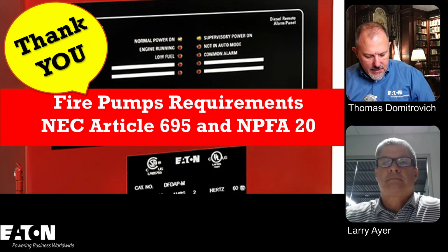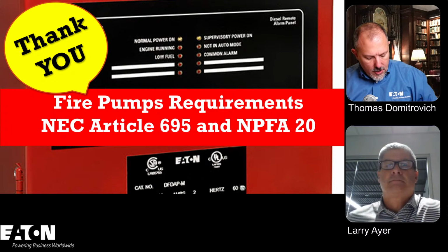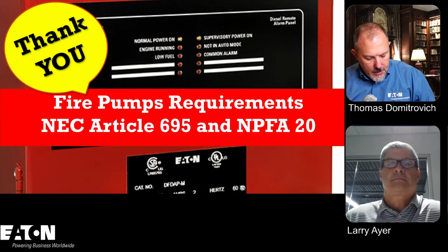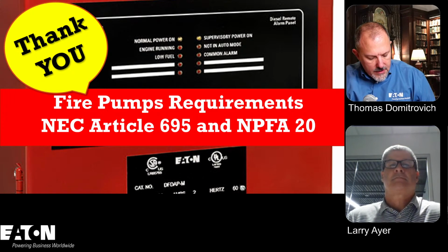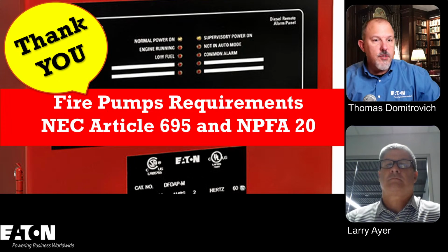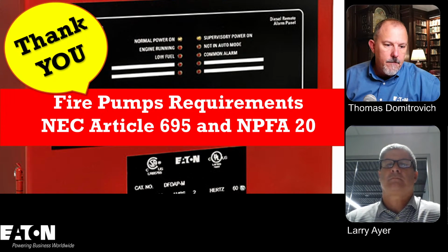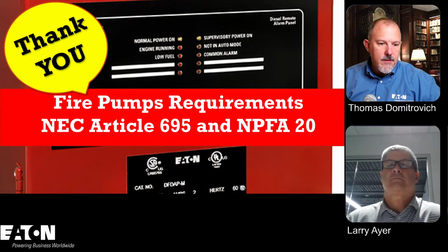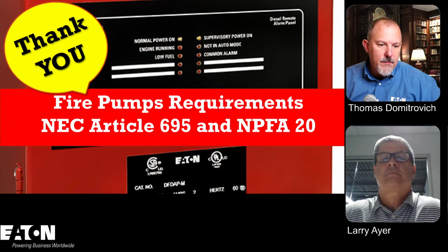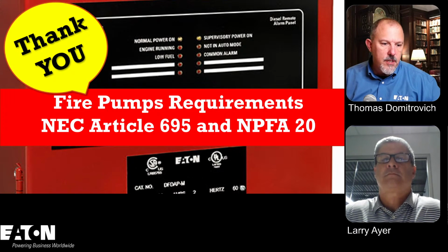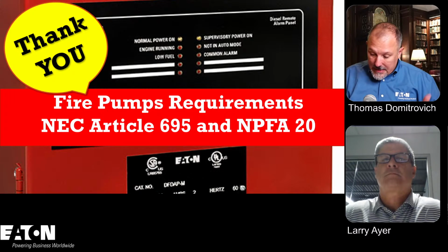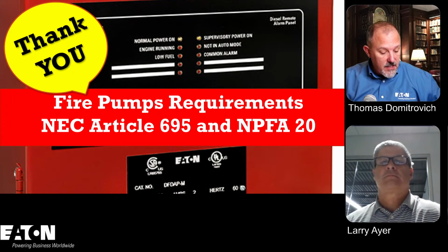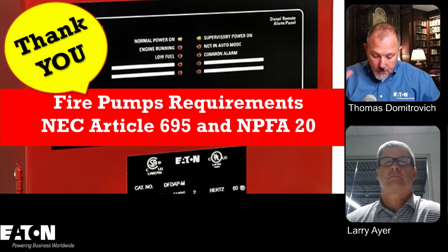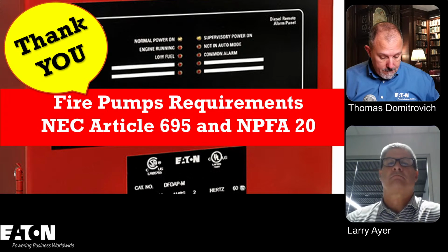It says in 700.5(C) that automatic transfer switches shall be electrically operated and mechanically held. Automatic transfer switches shall not be permitted to be reconditioned. And then in (A), it says that it has to be designed and installed to prevent the inadvertent. It says listed and marked for emergency use, but there's no equivalent. Mather says he found in the white book that there is a category code XNVE for transfer switches for use with fire pump motor circuits, and they probably exist, but there's nothing that I can find in 695 that says it has to be listed for fire pump applications. I could be missing it, but I don't see it, Larry. I really don't.